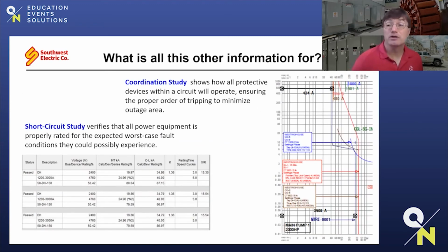The arc flash assessment also includes some other study information that's very handy. One is the short circuit study. This verifies that, based on all of these simulated faults throughout the system and the fault currents that are calculated, the equipment seeing those faults is rated high enough to handle and operate properly under those fault conditions. Quite often, older facilities have equipment at a certain fault level rating, but then through time, through expansion, through upgrades, they can actually outgrow their protective equipment and see higher fault currents than their equipment is rated to handle. In these cases, that equipment usually has to be upgraded or even replaced.